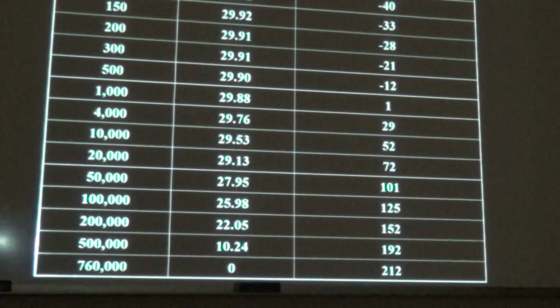Typically, let's say that the ambient temperature where the machine is, is 70 degrees. So from here to here, we were boiling water all the time. From 20,000 microns all the way to 500, as we were pulling that pump down. That's why when you turn on the vacuum pump, one of the first things you start to see really quick around here, because we're using very small systems, is steam coming out of the vacuum. That's because it's boiling already.